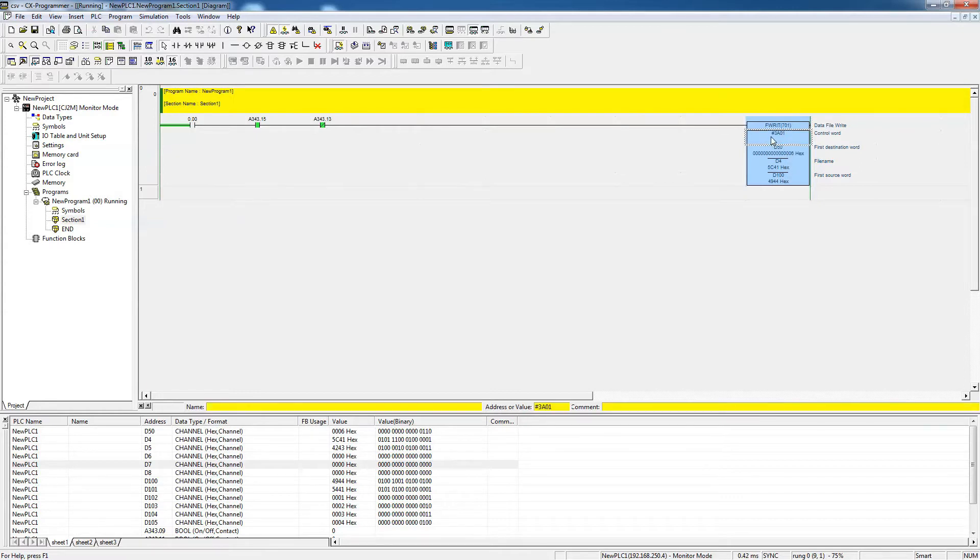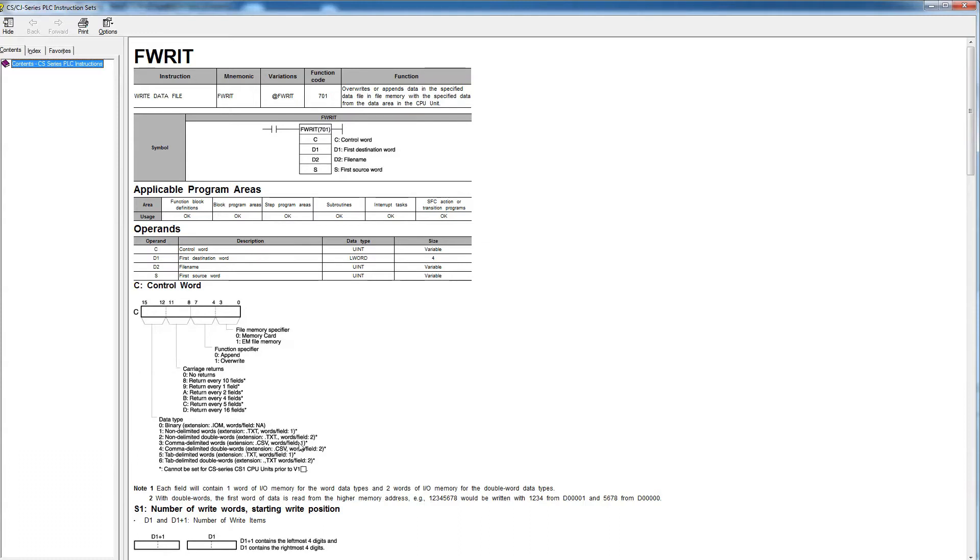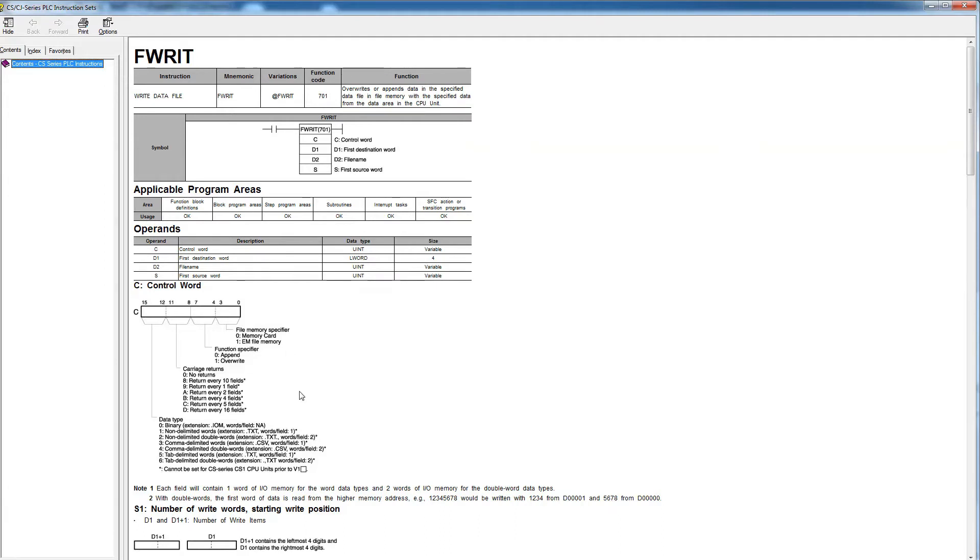For our purpose, the way I set up this block, is I put in here a hex three. So three basically means I want to create the file with CSV, the CSV extension. If we go back again to the help, we can see that the last four digits in here are dedicated for that purpose, and that's why I picked three, because I want to use comma delimited word, CSV, and I'm using one word per field. You could also pick the four if you want to have two words per field, and so forth. And then in the next four digits, I have A, because I want to return every two fields, because the idea is that I'm having basically a table that has two columns, and then it's going to have basically six rows.